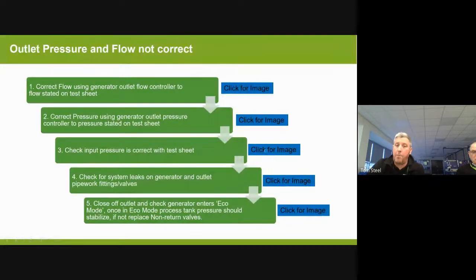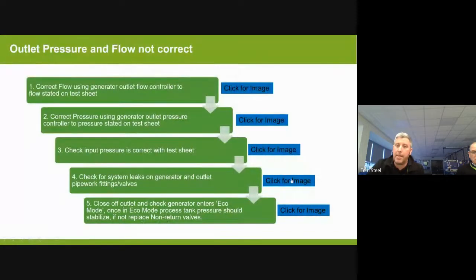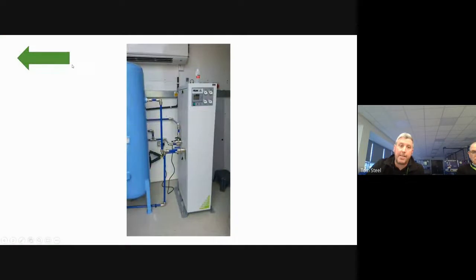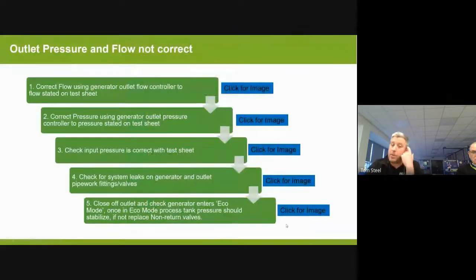Check the input pressure using the test sheet, and we'll check for system leaks using a leak detector. And once we've done that, we're going to close off the system and ensure it goes into eco mode. So once we've checked the input pressures, made sure they're correct, the input flow, we've made sure the compressor is maintained, all the filtration is maintained and working correctly, then we're going to make sure, using our test sheet, that the system is set up correctly and there's nothing been altered.